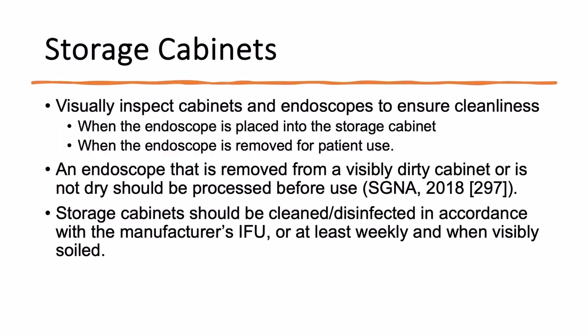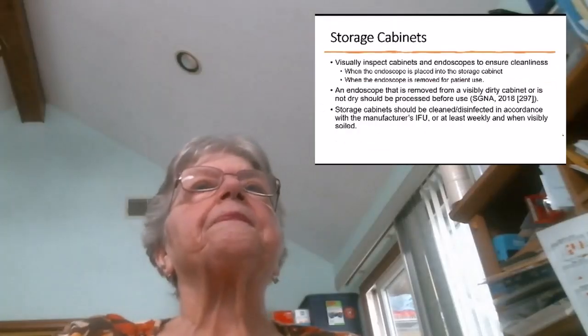You should visually inspect your cabinets and endoscopes to make sure they're clean when the endoscope is placed in the cabinet and when it's removed for patient use. An endoscope that's removed from a visibly dirty cabinet or is not dry should be reprocessed before it is used. And storage cabinets should be cleaned and disinfected according to the manufacturer's instructions, or at least weekly and when visibly soiled, and make sure that cleaning is documented.